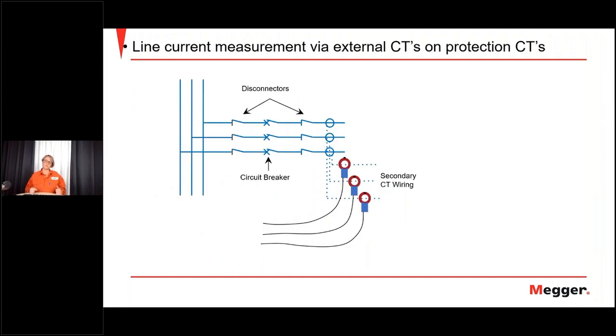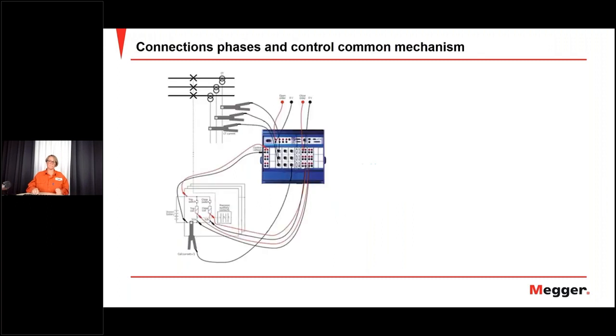So what do you do? Yeah, you connect current transformers in the secondary circuit of a current transformer, preferably the protection CTs. And you connect a current clamp in the control circuit. Here we have a common mechanism. We also measure the voltage here in the circuit. And often it is like this. You can't control it from the instrument. You need to control it from the station's control. But then you still can catch the current by using a current clamp.